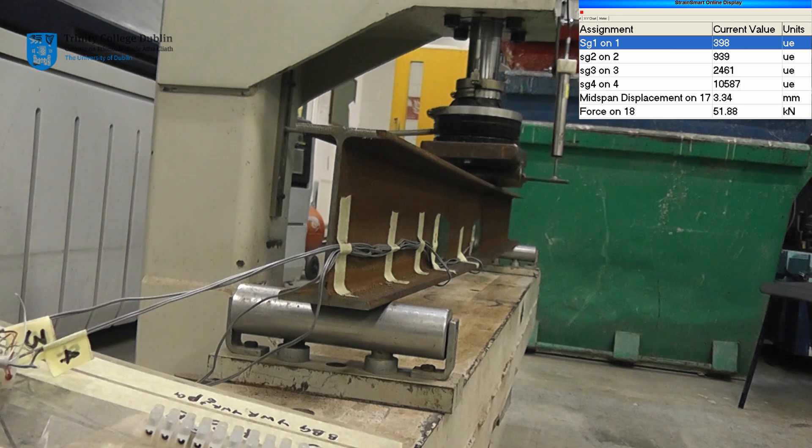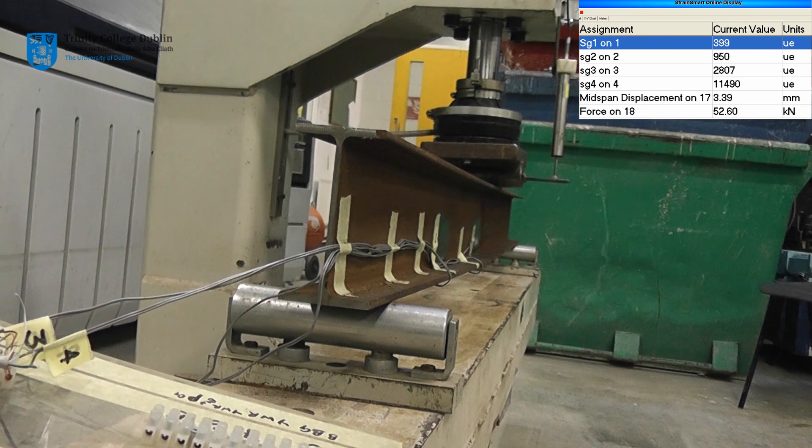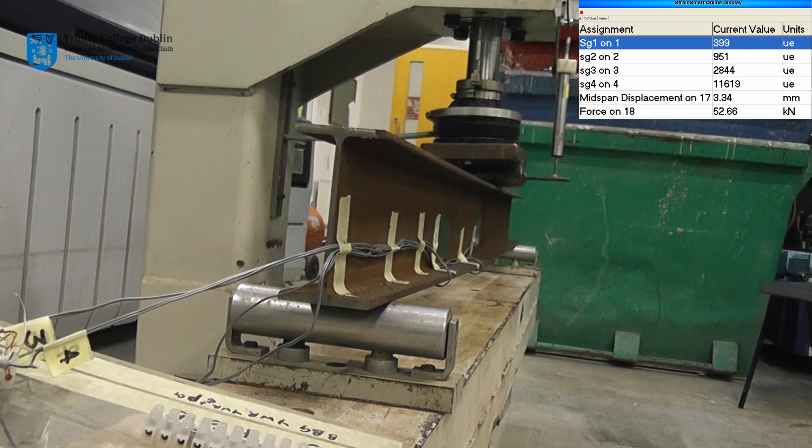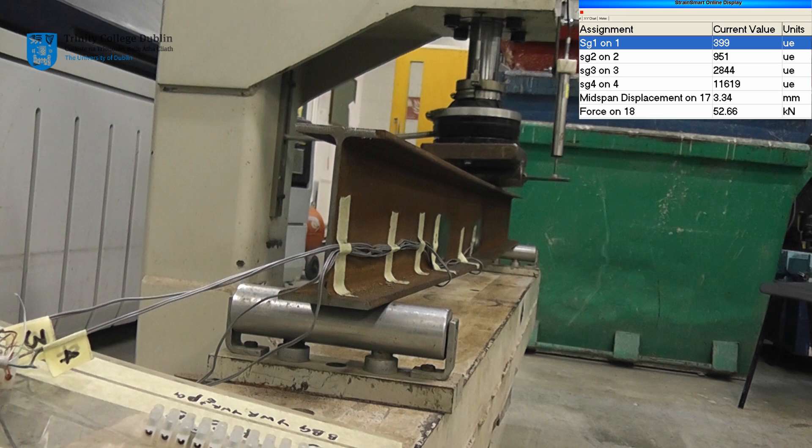Local compression failure along the top flange causes the test machine loading ram to rotate. This brings about a perceived reduction in displacement as the side of the loading ram holding the LVDT rises. However, this is not a real decrease in displacement. Displacement data from this point forward should be disregarded.